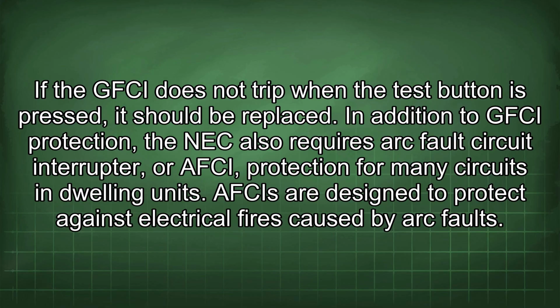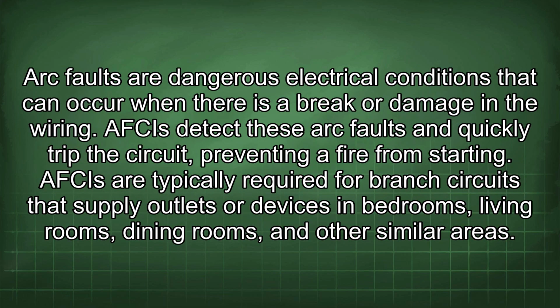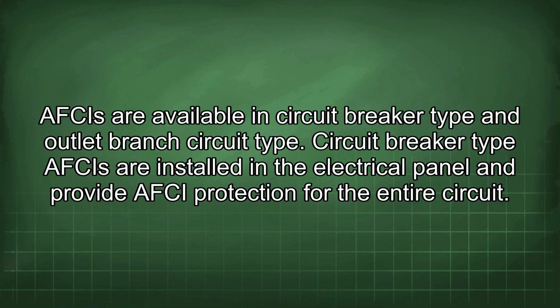In addition to GFCI protection, the NEC also requires arc fault circuit interrupter, or AFCI, protection for many circuits in dwelling units. AFCIs are designed to protect against electrical fires caused by arc faults. Arc faults are dangerous electrical conditions that can occur when there is a break or damage in the wiring. AFCIs detect these arc faults and quickly trip the circuit, preventing a fire from starting. AFCIs are typically required for branch circuits that supply outlets or devices in bedrooms, living rooms, dining rooms, and other similar areas. AFCIs are available in circuit breaker type and outlet branch circuit type.